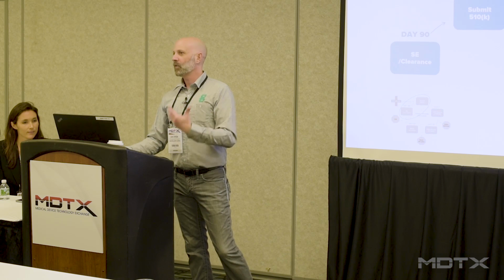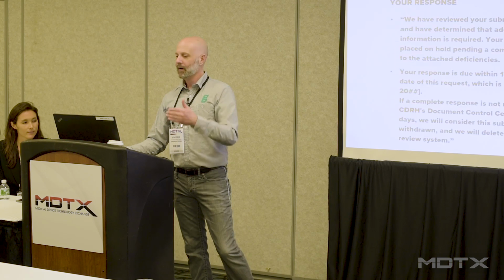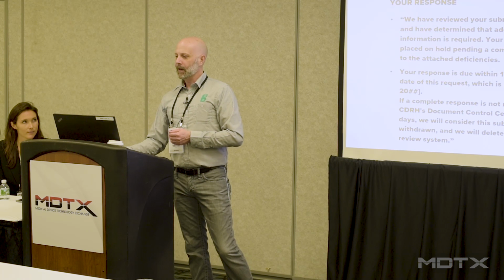Oh, so it's a good day on your 510K when they start asking you to update your 510K summary, because the 510K summary is what is going to be on the FDA website for your product. When they start asking you to make some adjustments to your 510K summary, in my experience that means we're at the last little bit of this 510K submission. So that's actually a good thing. And I'm telling you, the words matter. So just keep that in mind.